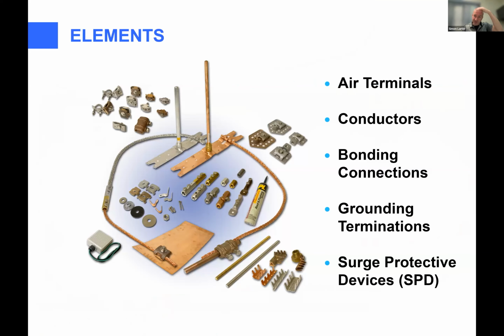Here are the elements of a lightning protection system. Starting from the top, you've got air terminals, lightning rods, strike termination devices. They're called multiple things, air termination rods, there's lots of terms for them. You can call them lightning rods, that's one of the easiest, but we generally call them air terminals as an industry term of art. That's the top, that's what captures the lightning strike initially. They assist in developing those counter leaders, I'll tell you why in a second, but that's why we put those up top. They're the things that initially take the lightning strike, and of course, we have to have a conductor to bring that charge safely to ground.